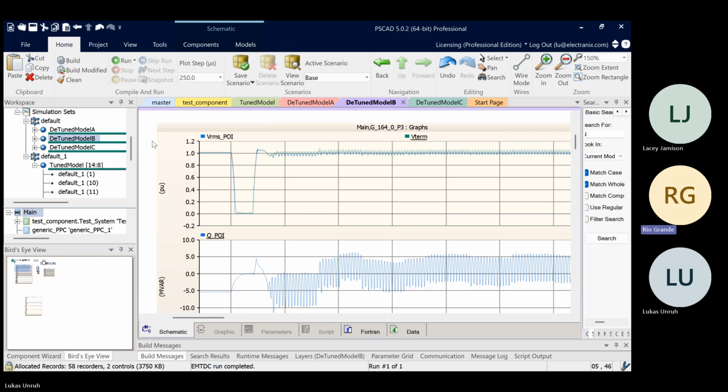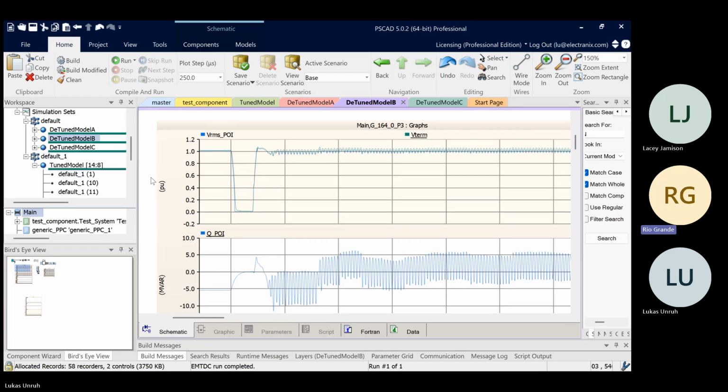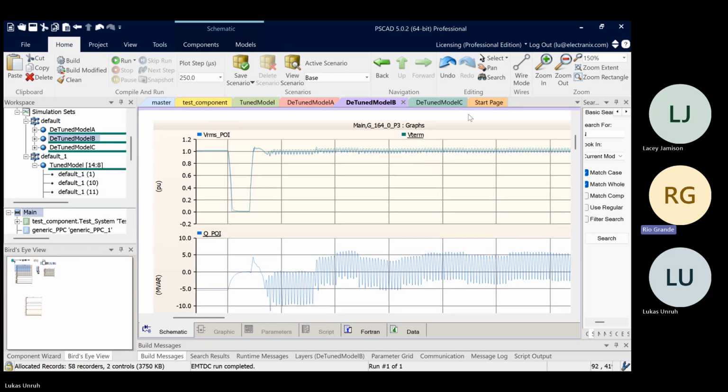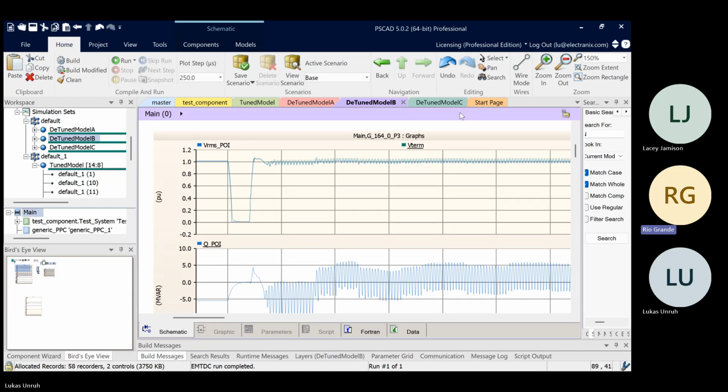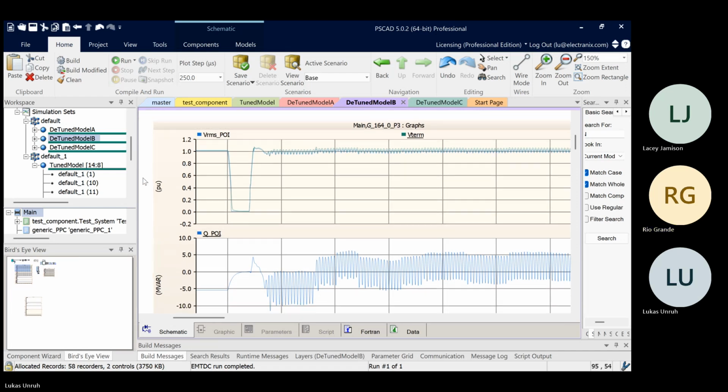If we see something like this and we know that the system strength is going to be at or below what we're testing here, we would probably just send it back right away. You can play around with it to figure out why it's doing what it's doing, but this is going to be very much in the domain of the manufacturer to tune this out of the inverter.